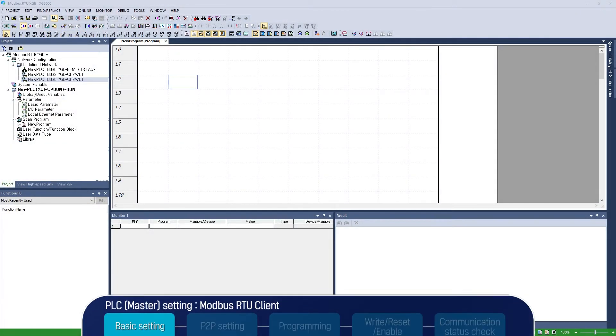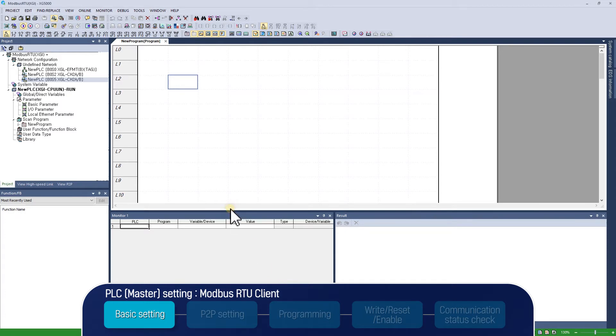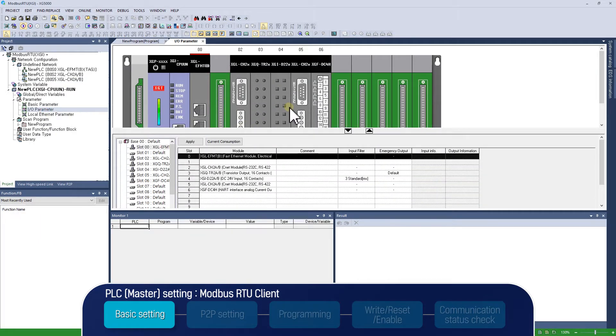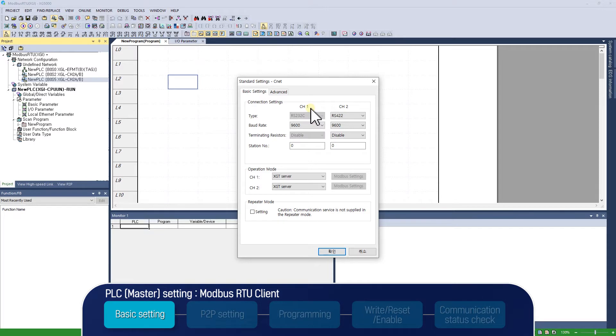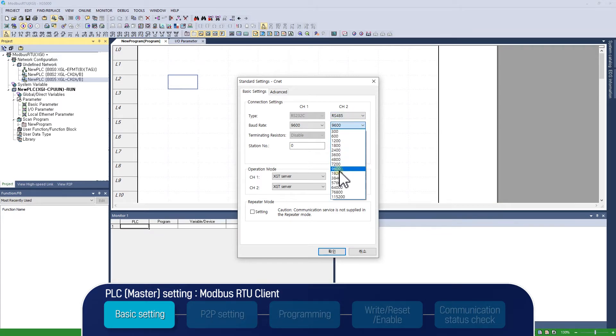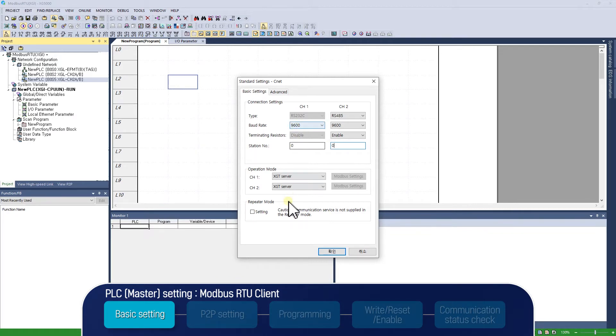Here comes PLC communication setup, standard and P2P setting of CNET. You could find I/O module information on I/O parameter in XG5000 project window. Double-click CNET module at slot number 5 and base number 0 in I/O module and do standard settings of CNET module with basic and advanced tab. CNET module has two channels, and here we are going to use channel 2. Select RS-485 in type, 9600 in baud rate, enable in terminating resistors, and put 0 in station number in connection settings of basic settings. Here PLC is located at the terminal, which we are supposed to enable the terminal resistor.